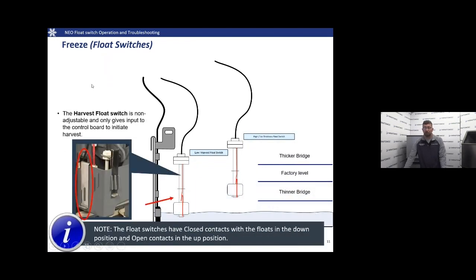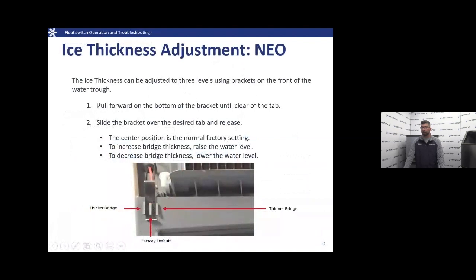The harvest float is not adjustable — that's the purpose of that cutout in the bracket. Its only job is to tell the control board that we are out of water, the ice is thick enough, and it's time to go into the harvest cycle. Remember that the float switches have closed contacts with the float in the down position and they are open in the up position. To adjust the ice thickness float: the leftmost bracket notch gives a thicker bridge, the rightmost gives a thinner bridge, and the middle is our factory setting.